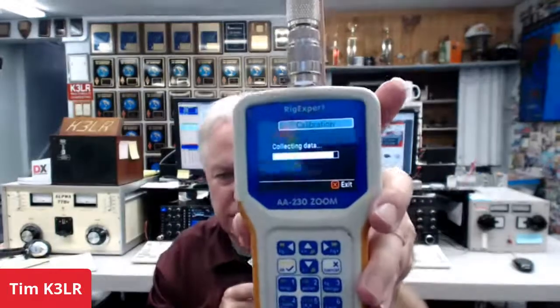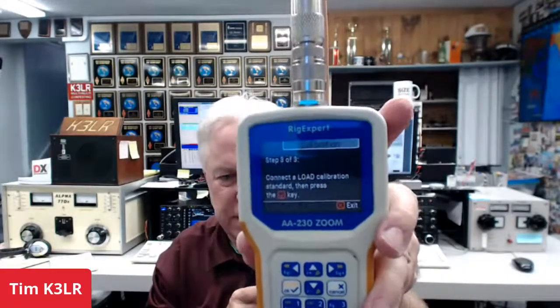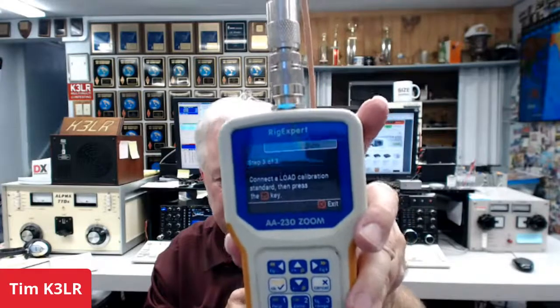So we're moving the reference plane to the end of this test cable, which is what we're going to hook to the base of the vertical. And then we want to stand away from the vertical so that we don't influence the measurements. And we hope to have some video of that for you on Friday. So let's see what we get here now. We're on step 3 of 3. And it says, now connect the load calibration standard. So here comes the load. And let's put the load on. I'm going to take the short off first. And then this is a good 50 ohm resistor, non-inductive. Okay, can't be inductive. So this is the 50 ohm load. We go ahead and we hit the check mark again.